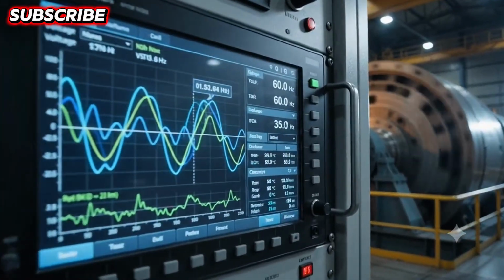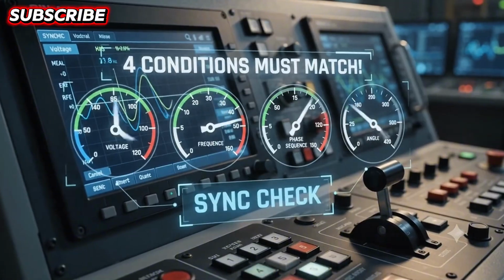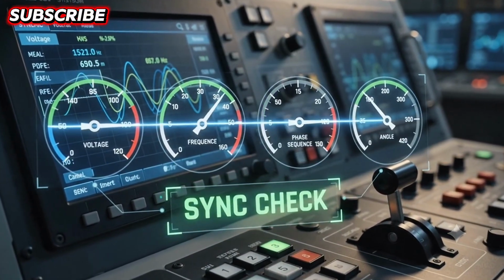Before connecting a generator to the grid, voltage, frequency, phase sequence, and phase angle must match.